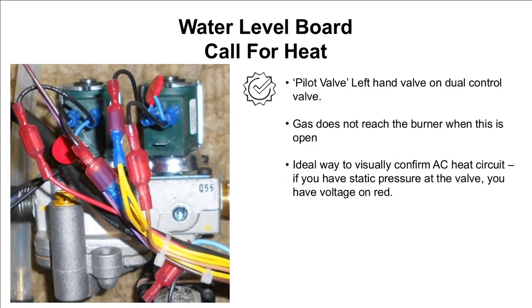The next spot is the pilot valve, which is the left-hand valve here. Now, this is one of the reasons that I had you connect your manometer before doing any other troubleshooting. When your AC circuit is satisfied, you will register static pressure on your manometer. It's a really easy way to test if one side of the heat circuit is working. And just as a side note, gas is not being supplied to the burner when this pilot valve is open. It is just sitting and waiting for our second valve, which is the main valve here, to open.